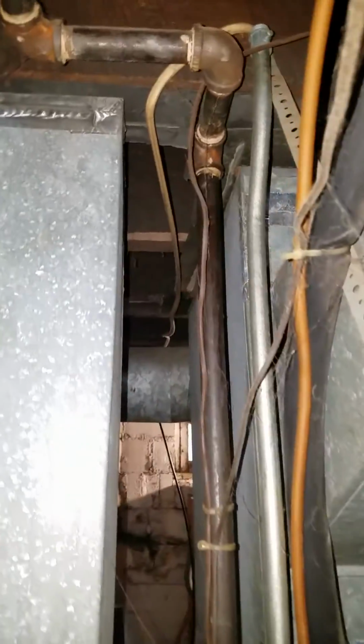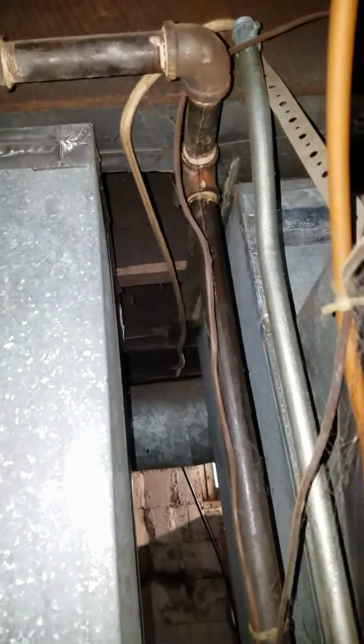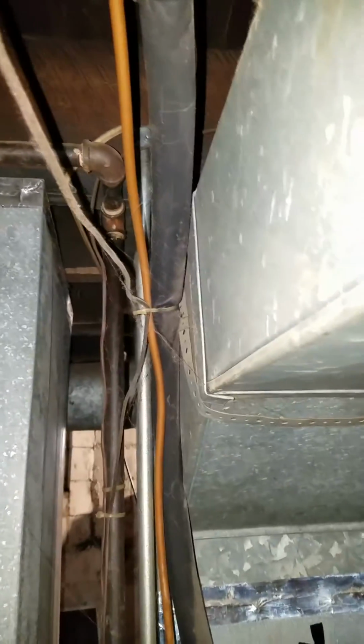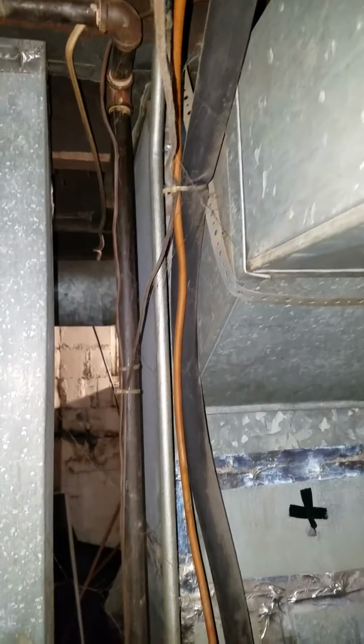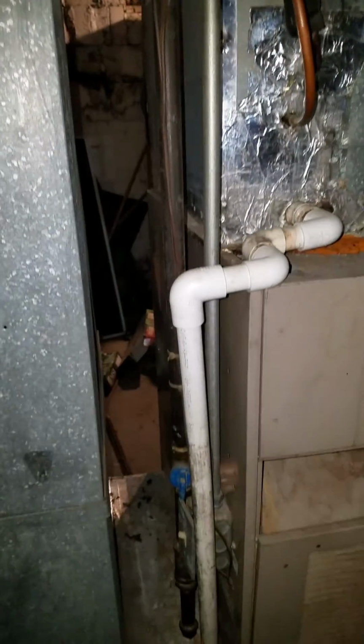On your return, we used to have a pan right there. That's no longer panned. That's kind of open, but you still have this return drawing from that, and that is about a 24 by 8. So that's what you look like in your return. It's really kind of a little bit of a mess there. So that needs to have a piece of panning put back across there, so that you're not just drawing right out of the basement like that. We're coming down like so.